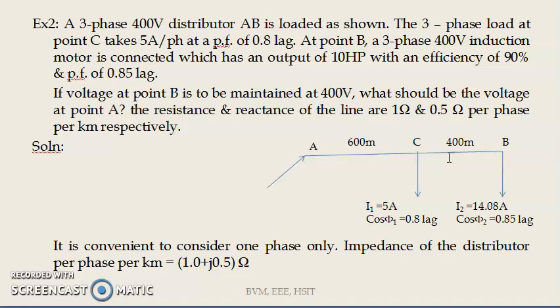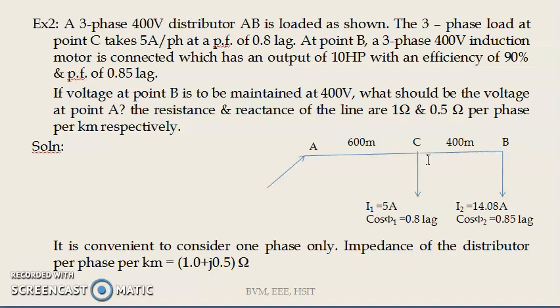In other words, VA equals VB plus the voltage drop in section CB plus the voltage drop in section AC. To get the voltage drop in section CB, you multiply the current in section CB by its impedance: ZCB multiplied by ICB. ICB is I2, which I have written here as 14.08 amps. I will now show how to obtain this value.